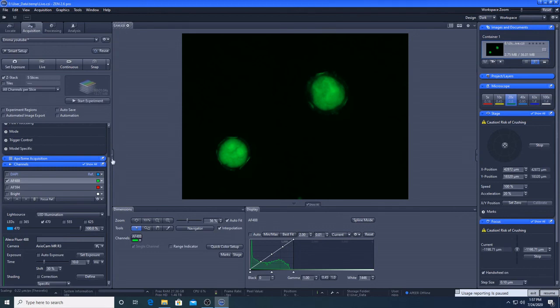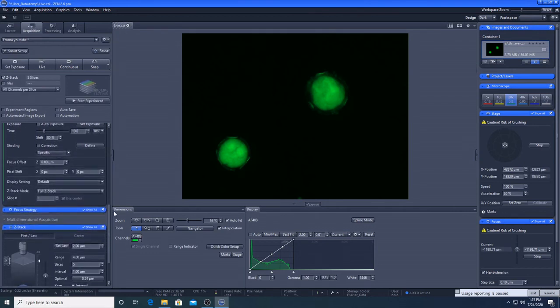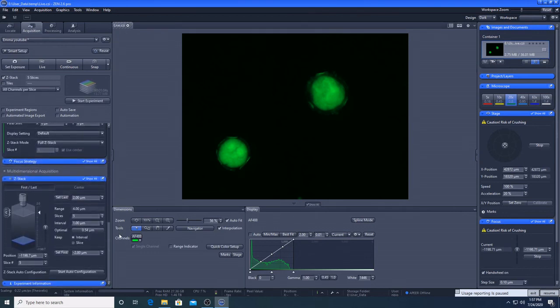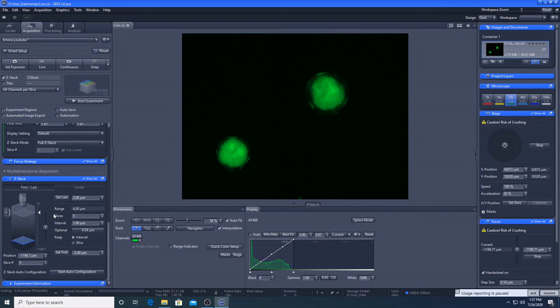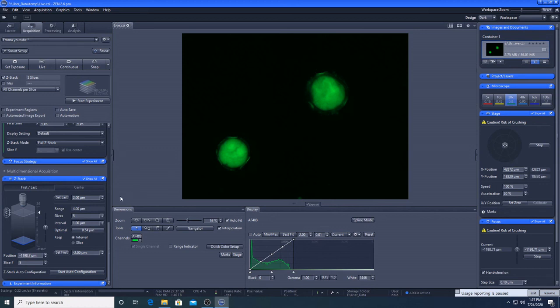So now we're going to talk about z-stacks. So I'm going to click on the z-stack here and I'm going to scroll down to this menu. So a z-stack is a way of taking a 3d image or it is a way of taking multiple layers for if you have a particularly thick sample of multiple focal planes. If you need a true 3d image I recommend using a confocal microscope. Using a z-stack on this kind of machine is more helpful for just getting detail at different focal planes rather than viewing them all at once.